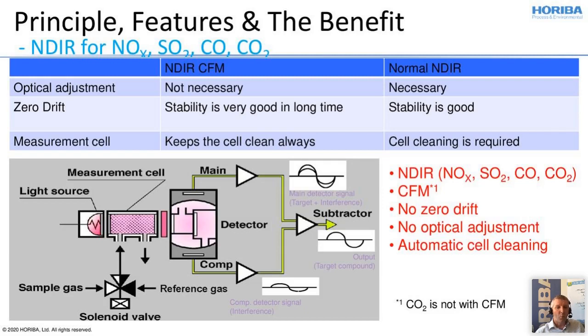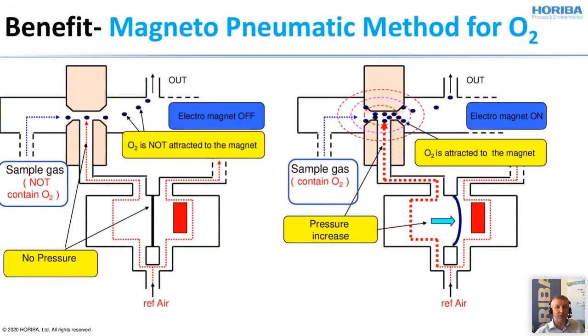So, what is the basic method we are using for oxygen? Oxygen is a paramagnetic gas. In an uneven magnetic field, its molecules are attracted to the stronger portion of the magnetic field, increasing the pressure in that portion. The pressure increase at this time is taken out from the magnetic field using a non-paramagnetic gas such as nitrogen. It is detected by a capacitive microphone detector and then converted into electric signals.